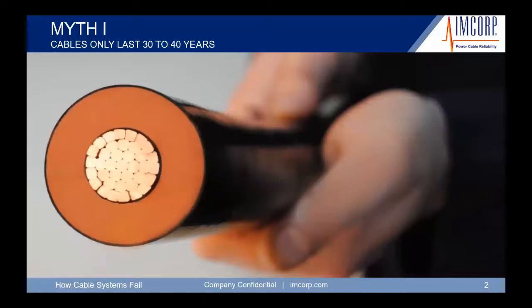So the first myth is that cables last 30 to 40 years. We know today in the Houston market, we're testing cables that were installed before 1979. If you compare a medium voltage cable to a low voltage cable, a low voltage cable is very simple. It's got a conductor and an insulating material or jacket. Medium voltage cable is a little bit more complex. Not only do you have a conductor, but you have a strand shield, your insulation, and your semiconductive material.